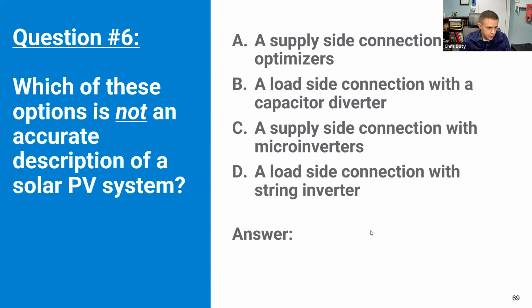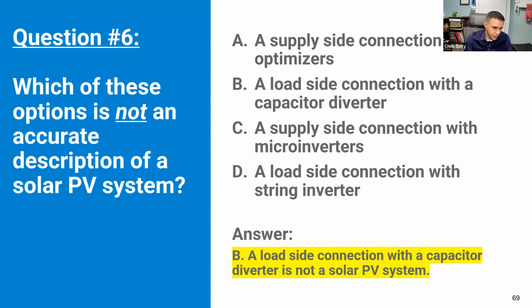We'll keep moving through here. The one that is not is a load side connection with a capacitor diverter. That is not a real thing. A capacitor diverter. You can have a supply side connection with optimizers. It doesn't really matter where the connection is if you have optimizers, inverters, or a string inverter. Everything just has to be compatible with each other, and the connection and the type of inverter is kind of irrelevant. But yeah, the one with the capacitor diverter is not a solar PV system.